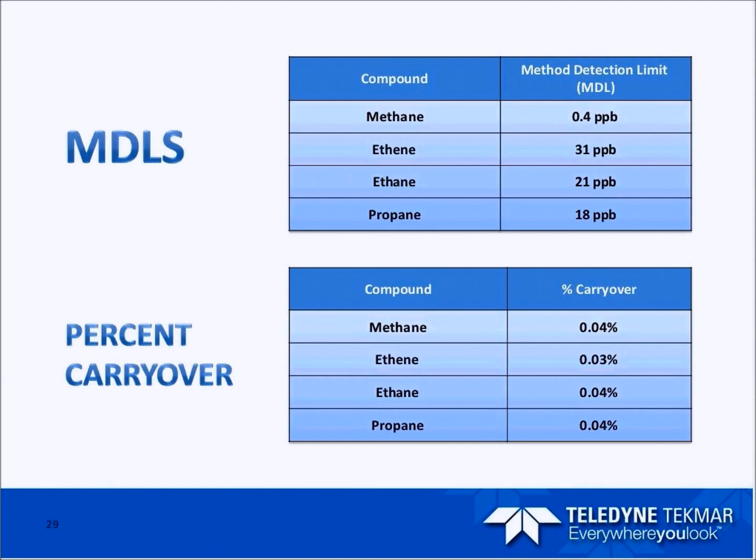It's going to really hurt this analysis, specifically because of the dynamic range. The concentration we run the carryover study on is so high that you hope you can still get a workable reporting limit out of it. And it seems that we can get pretty good reporting limits with this analysis. So the carryover is really low, which is good.